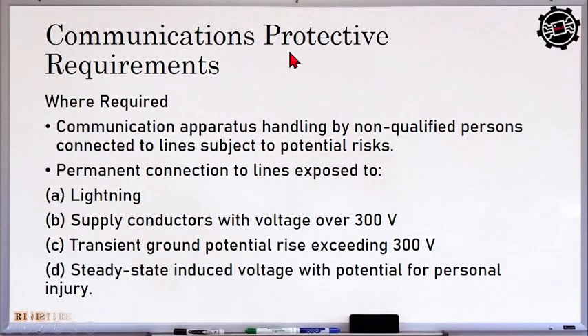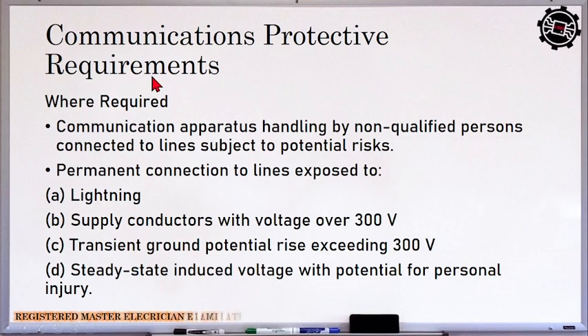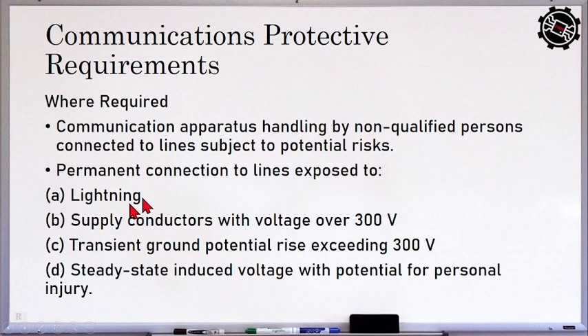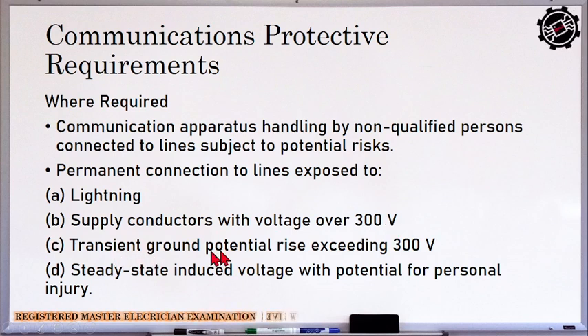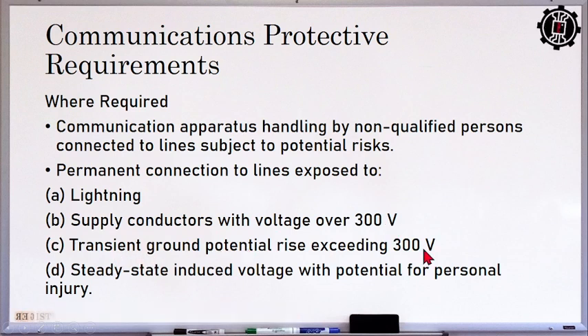Then communication protective requirements, no? So this is now for the communication lines. So when required, communication apparatus handling by non-qualified persons connected to lines subject to potential risk. So permanent connection to lines exposed to lightning, no? So yung mga pwedeng matamaan ng kidlat. Supply conductors with voltage over 300 volts. Transient ground potential rise exceeding 300 volts. Tapos meron siyang steady state induced voltage with potential for personal injury.